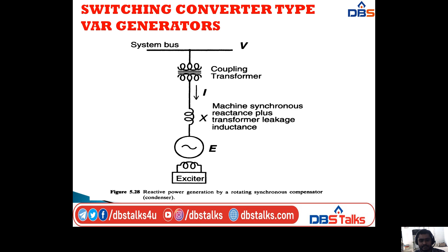For purely reactive power flow, the three-phase induced electromotive forces, EA, EB and EC, of the synchronous rotating machine are in phase with the system voltages VA, VB and VC. The reactive current I drawn by the synchronous compensator is determined by the magnitude of the system voltage V, the internal voltage E, and the total circuit reactance X.